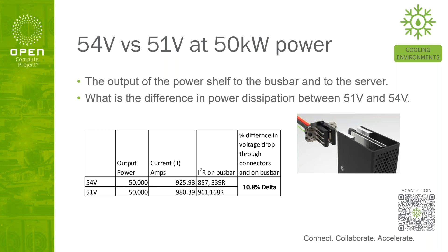But the real reason I want to do this is that when you look at the voltage drop across the connectors and down the bus bar, that voltage drop is simply I squared R. The difference between 54 volts and 51 volts with this I squared R turns out to be about 10.8% difference in the voltage drop in that connector or down that bus bar, and that translates directly to temperature rise. So by just changing from 51 volts to 54 volts, we can push that connector a little farther, or have more margin in the connector, when we're already getting close to the edges on those connectors and that bus bar.